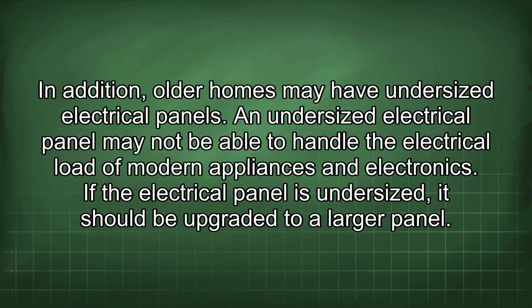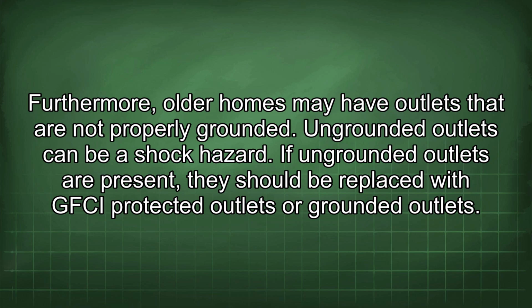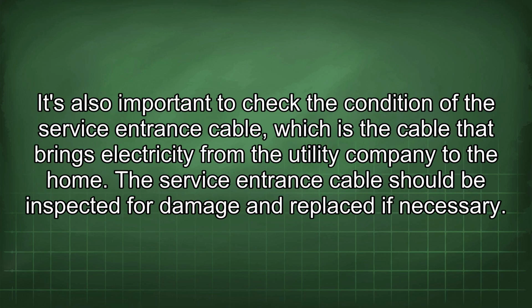In addition, older homes may have undersized electrical panels. An undersized electrical panel may not be able to handle the electrical load of modern appliances and electronics. If the electrical panel is undersized, it should be upgraded to a larger panel. Furthermore, older homes may have outlets that are not properly grounded. Ungrounded outlets can be a shock hazard. If ungrounded outlets are present, they should be replaced with GFCI protected outlets or grounded outlets. It's also important to check the condition of the service entrance cable, which is the cable that brings electricity from the utility company to the home. The service entrance cable should be inspected for damage and replaced if necessary.